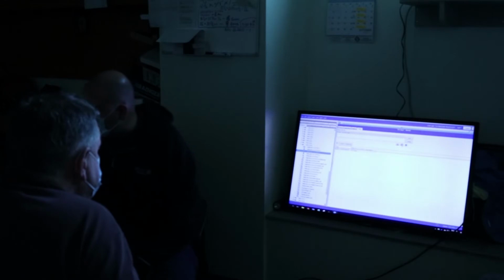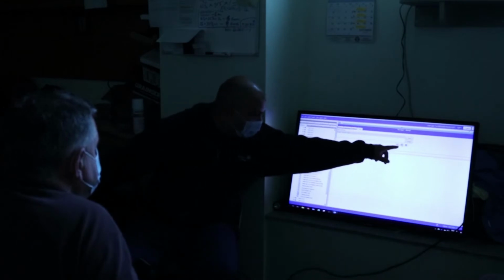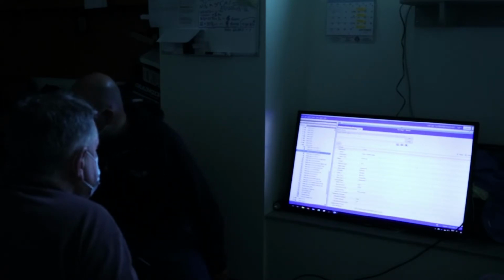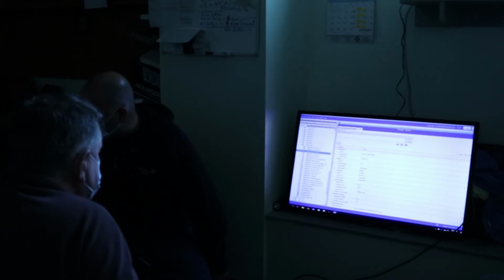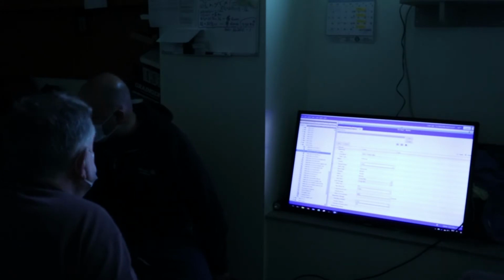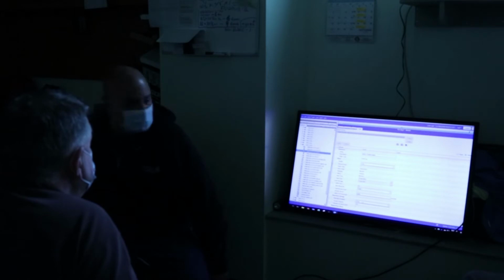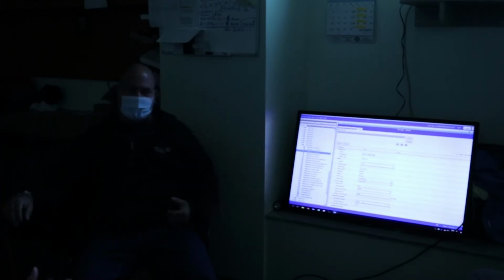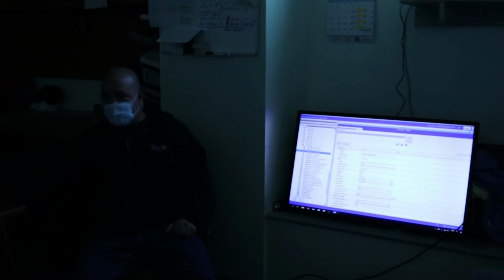If you wanted to put it into a table, you click on the middle one that looks like a little table. And if I want to edit the data, I click on the last one, and you need to go to advanced. Now, if I wanted to change the time, I can edit it here, like if I wanted to make it faster or slower. And if I wanted to enable or disable a repository, I can do it here. So if you add a trend and say, oh, the half hour is not long enough, or I need to keep this for a week, so let me enable it, you can go in and edit it. You don't have to create a new one.